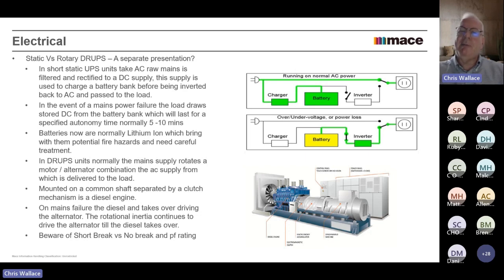It wouldn't normally go through that bypass line. And simply what happens is your charger, or you have a rectifier which changes AC to DC, then you have an inverter which inverts it back from DC into AC. And in the event that the power goes off, someone digs up the cable in the street, basically your mains pulls the power out of the batteries via the inverter, and the lights don't go off.